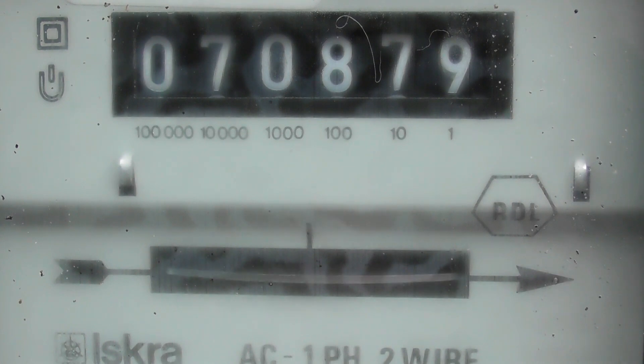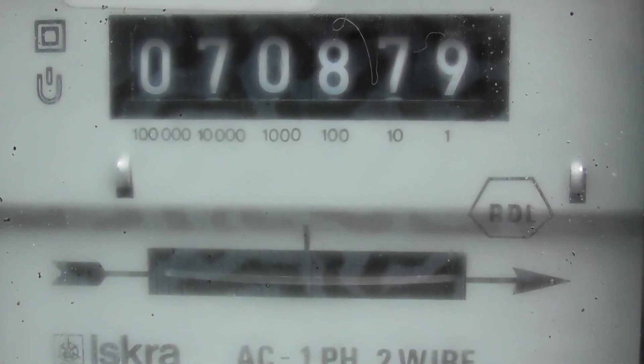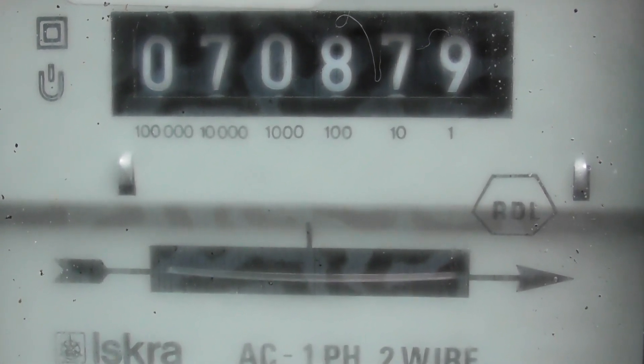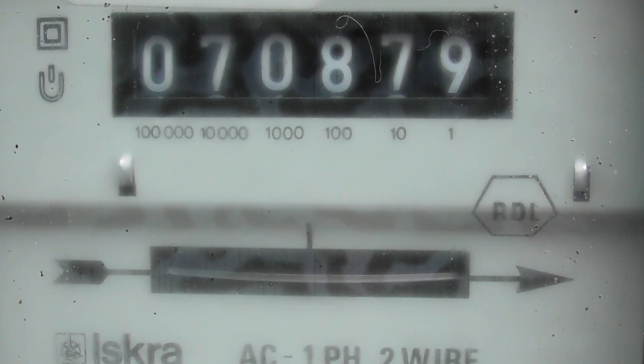So if you have solar panels or your generator, or you're putting something back in the grid through inverters, your meter will go backwards. Nowadays utilities put two or four quadrant metering in with electronic meters, so you can actually get paid for the power you put back in the grid. Or you can put two meters back to back as well, which is done sometimes—one meter measures one way and the other measures the other way.